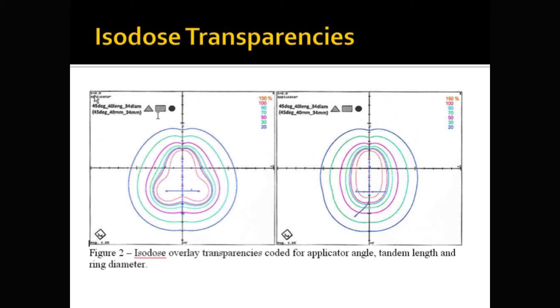This is an example of one of the Isodose overlays. So they would place the device in the simulator. They would take AP and lateral radiographs. The device overlays are coded with the angle of the device, the tandem length, and the ring diameter. And we pre-printed Isodose curves of 150%, 100%, 90%, 70% to duplicate the ICRU point A dose, the bladder and rectal points.